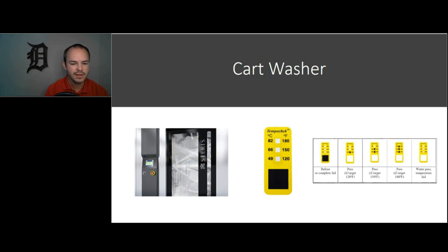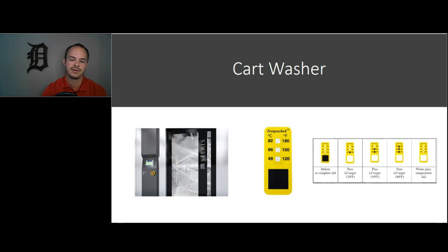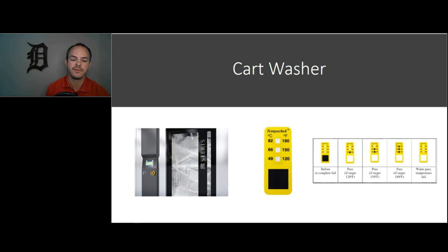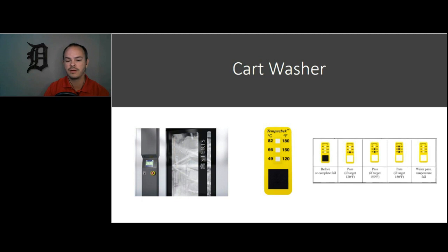In an ASC setting, you may or may not have a cart washer. If you do, you should be checking to make sure it's working just like an instrument washer — it too can fail. A simple test shows that water impingement is reaching the hard-to-reach areas within your case carts. The little black square on the test will turn white if water is reaching it. It can also show you what temperature your washer water reached during the cycle — for low-level thermal disinfection, you want that 180-degree indicator to change accordingly.